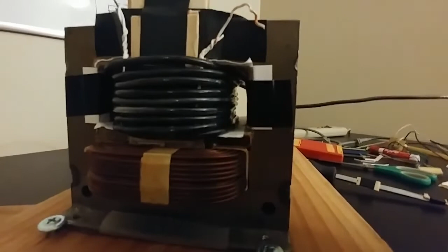As the transformer is getting wound, even though we can get things really straight using that screwdriver to press against it, the coil itself is actually moving a little bit around the core. So to fix that, I just stick a shim in it and pry against that from the other side.